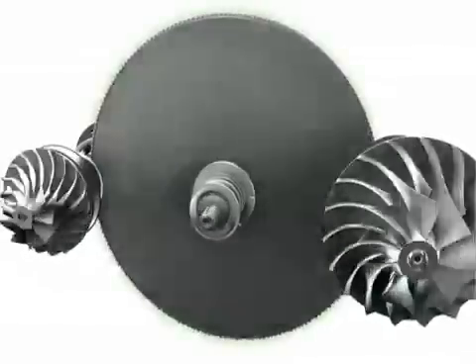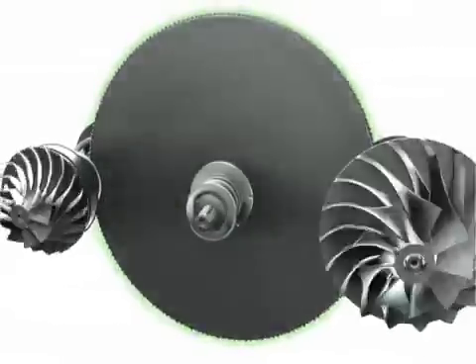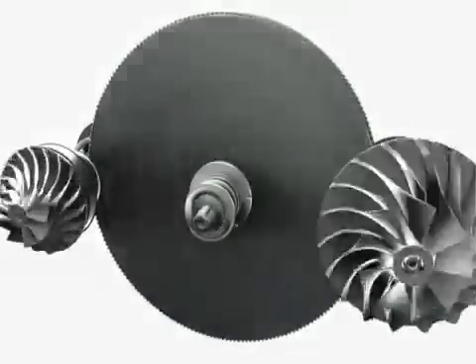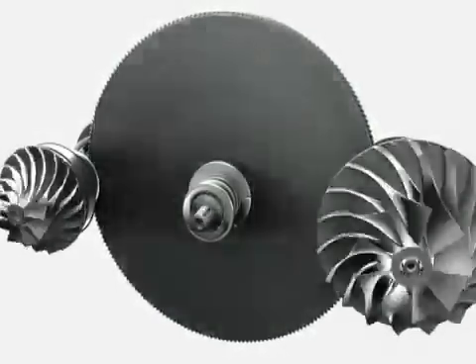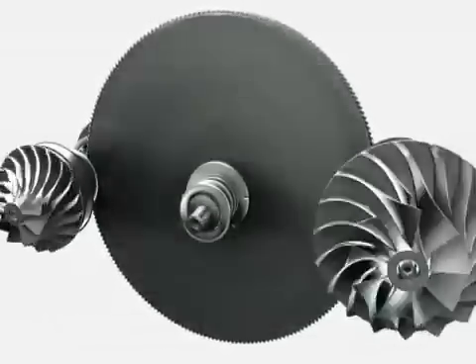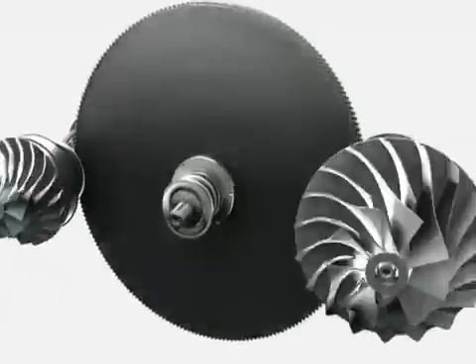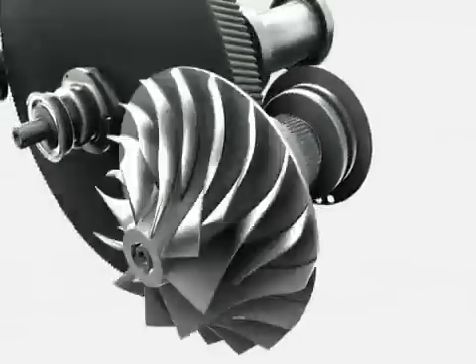The rotating assembly is driven by an extremely durable bull gear. This robust precision ground AGMA-rated bull gear has been through hardened to maximize life up to 25 years. It's connected to the motor via a flexible gear or dry type maintenance free coupling. The low speed bull gear bearings add to the durability since no thrust is transferred to the bull gear shaft.